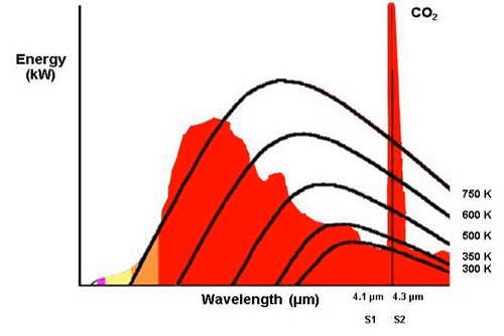In this case, one sensor looks at the 4.4 micrometer range while the other sensors look at reference wavelengths both above and below 4.4. This allows the detector to distinguish between non-flame IR sources and actual flames, which emit hot CO2 in the combustion process. As a result, both detection range and immunity to false alarms can be significantly increased. IR3 detectors can detect a 0.1 square meters (1 square foot) gasoline pan fire at up to 65 meters (215 feet) in less than 5 seconds.